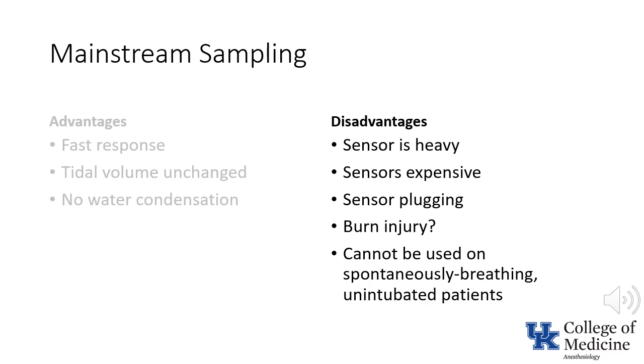Secretions may accumulate and plug the sensor, and burn injury may possibly occur because the sensor is heated. Furthermore, the mainstream capnometer has somewhat limited use since it cannot be used to measure end-tidal carbon dioxide in spontaneously breathing, non-intubated patients.